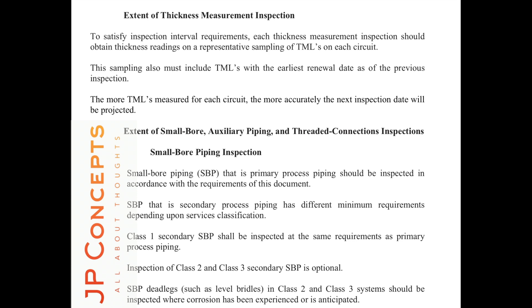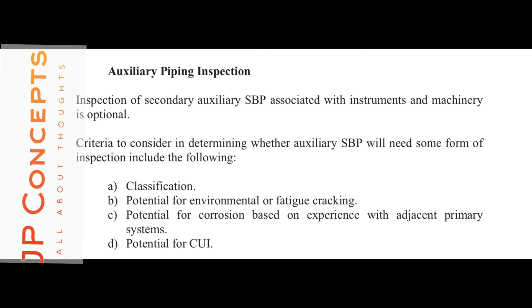Inspection of auxiliary piping. Inspection of secondary auxiliary small bore piping associated with instruments and machinery is optional. Criteria to consider in determining whether auxiliary small bore piping will need some form of inspection include the following: A. Classification. B. Potential for environmental or fatigue cracking. C. Potential for corrosion based on experience with adjacent primary systems. And the last one, D. Potential for corrosion under insulation. This is well explained in API 570 and 574.